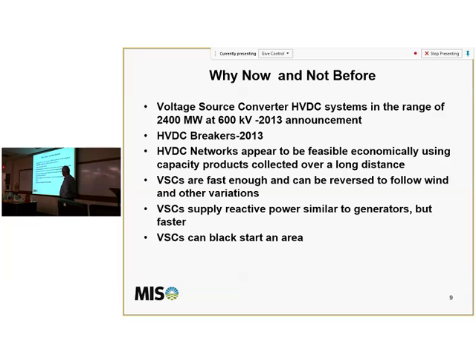The other thing is VSCs supply reactive power. They supply plus 35% to minus 50% of their rating at full power. And if you put a 50% capacitor on there, you can bring that all up to positive reactive support.